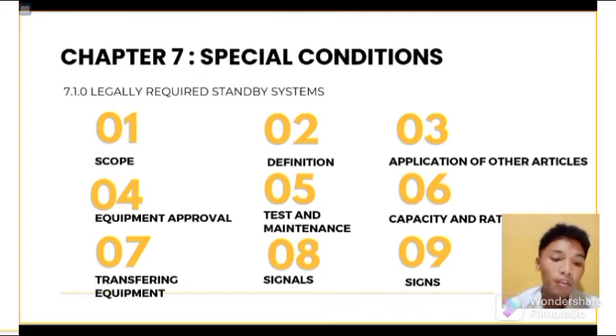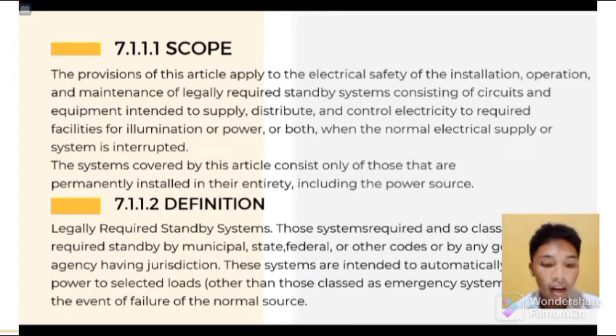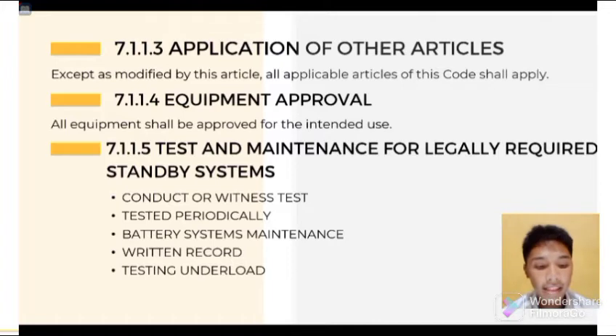So the systems covered by this article consist only of those that are permanently installed in their entirety, including the power source. By definition, legally required standby systems are those required and so classed as legally required standby by municipal, state, federal, or other codes or by any governmental agency having jurisdiction. These systems are intended to automatically supply power to selective loads, other than those classed as emergency systems, in the event of failure of the normal source. In the application of other articles, except as modified by this article, all applicable articles of this code shall be applied.